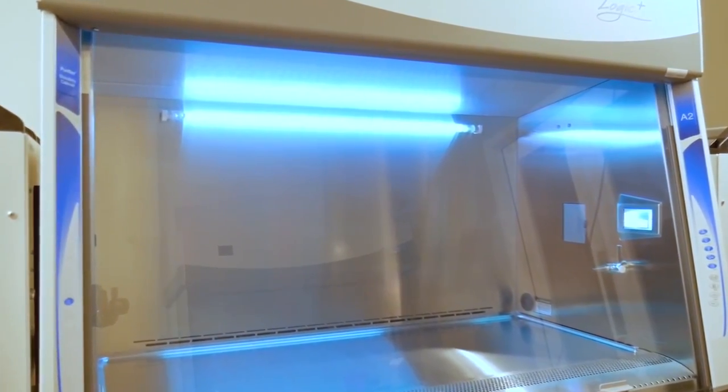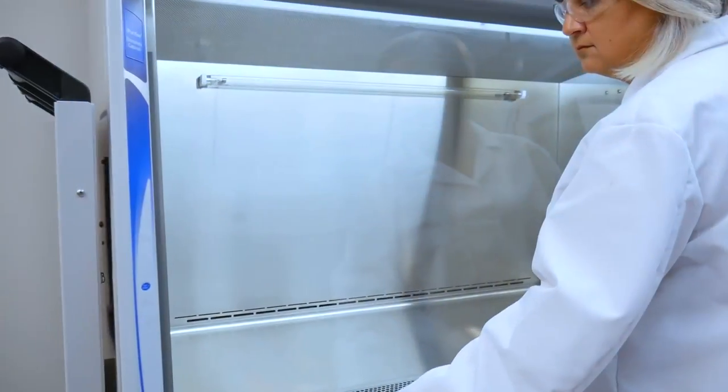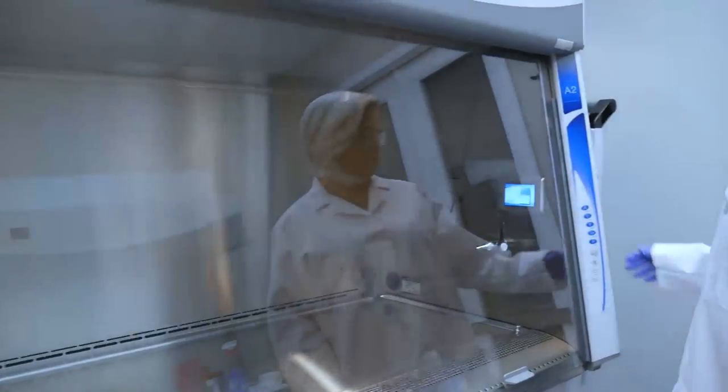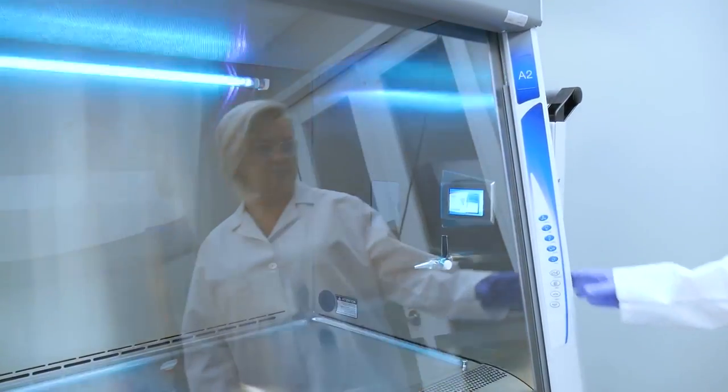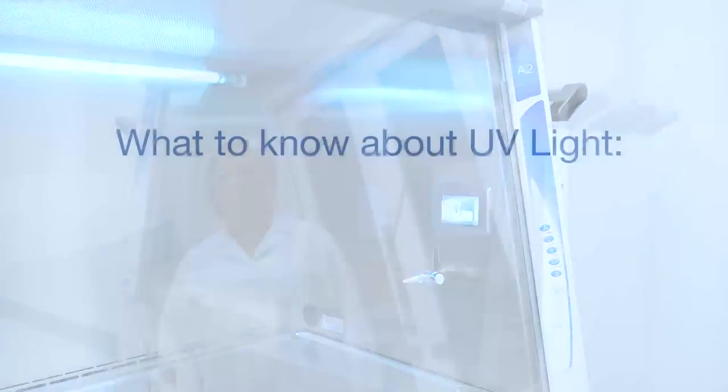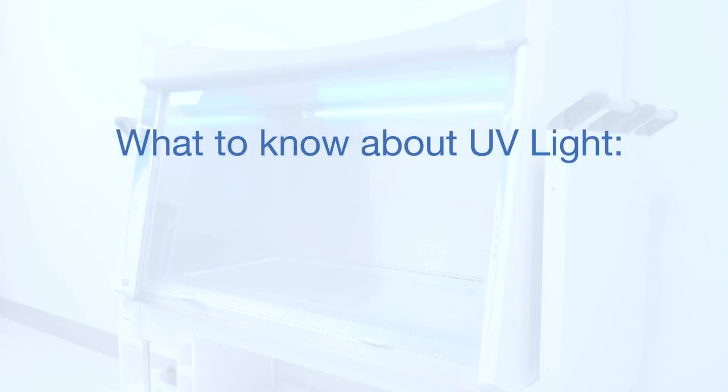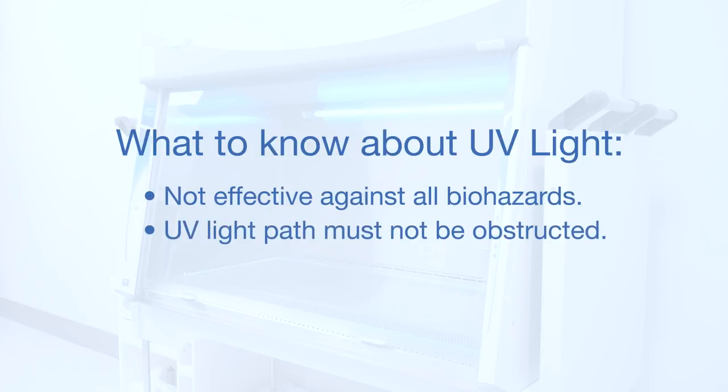Caution should be exercised when using UV light for disinfection of the cabinet. UV should never be the primary method of disinfection because of several limitations. UV is not effective against all biohazards. In order to work, the UV light path cannot be obstructed. Additionally, the bulb loses intensity over time and must be replaced regularly.